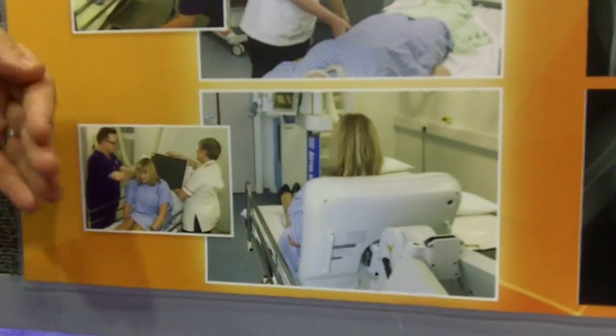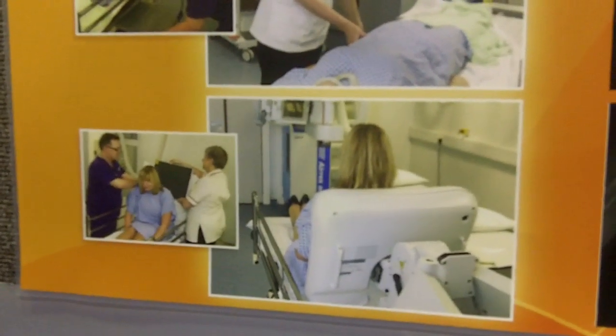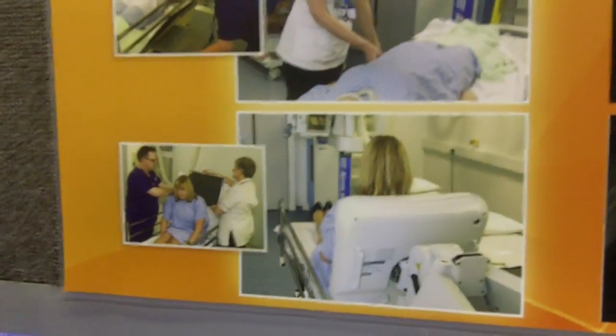It's then really quite easy to slide the bed underneath the detector, ease the patient forwards, lean them back onto that detector and use it quite simply as a film in all intents and purposes. The big difference is we're now using an AEC, we're using a grid, we're doing it with a high kV, and we're getting the best quality of images on these very, very difficult patients.